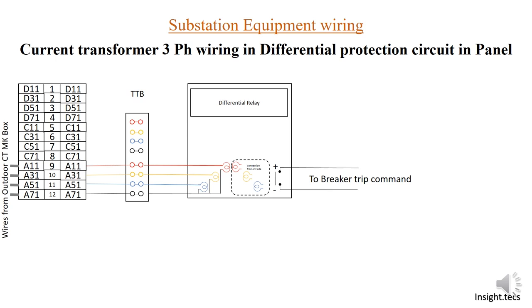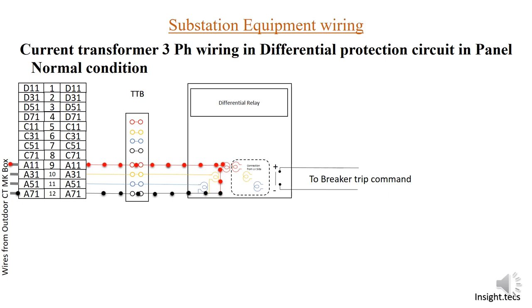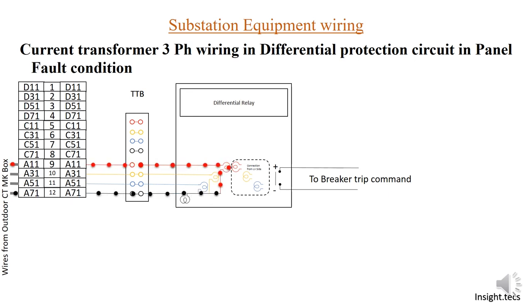For the differential protection circuit, during normal current flow, you can see normal current flowing on the HV side. A differential relay operates whenever there is a difference in the current flowing from the HV side and the LV side. When more current flows on the HV side, creating a difference between HV and LV currents, a trip command is sent to the breaker. The positive terminal meets the negative, the circuit is completed, and the breaker trips.